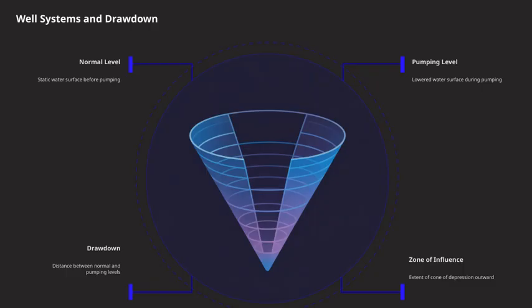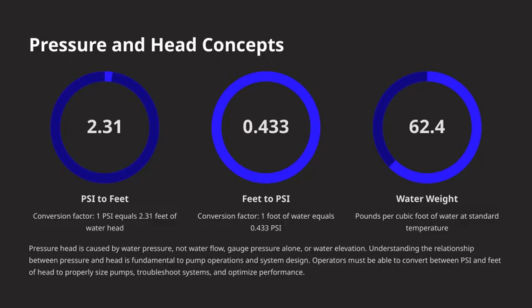It allows operators to identify potential problems early on and make adjustments to pumping rates or well field management, ensuring a sustainable water supply for the long term. Let's take a closer look at pressure and head concepts. Now, one key thing to remember is that 1 psi, or pounds per square inch, is equivalent to approximately 2.31 feet of water head. This conversion factor is really useful when we're working between pressure and the height of water, or head, in a system.